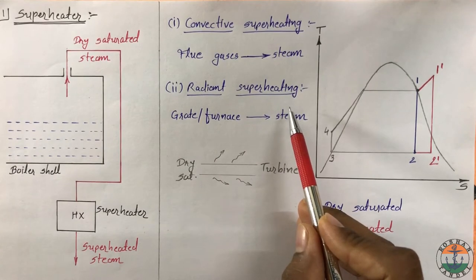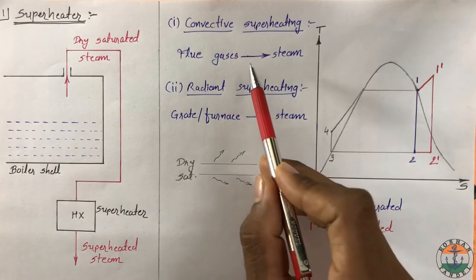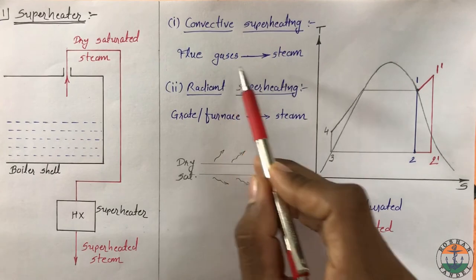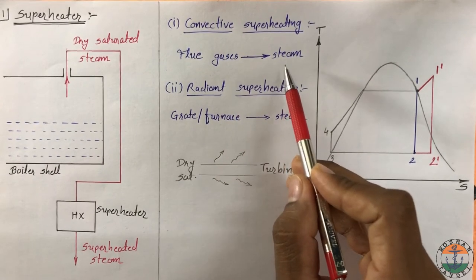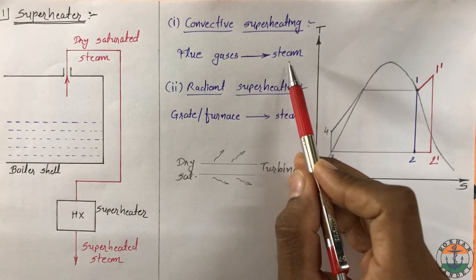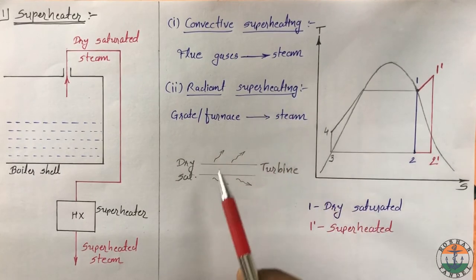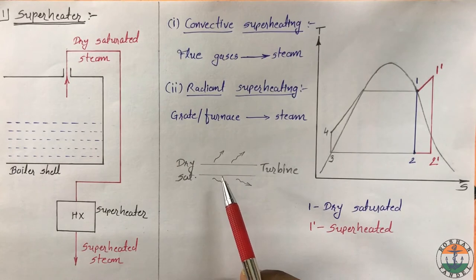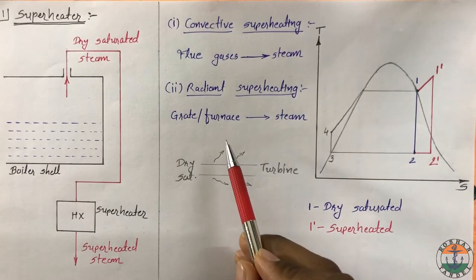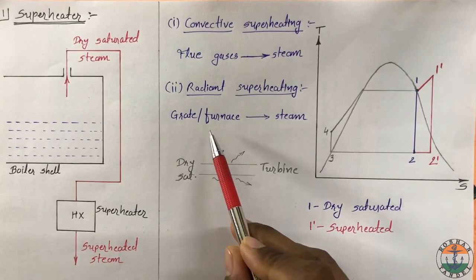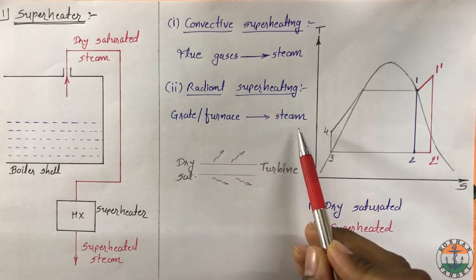In convective superheating, heat is transferred from flue gases to the steam to convert it into superheated steam. Whereas in radiant superheating, steam is passed just above the furnace or grate and heat transfer takes place by radiation to the steam.